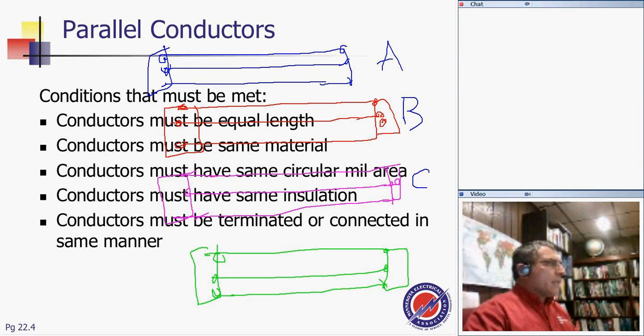These are your conductors that parallel, tied at the end. This is my neutral. This is my neutral. So each of these, these are three conductors. Each one of them, my friends, is 500 kcm. I like 500 kcm. The same thing, 500 kcm, 500 kcm. And let's just say the neutral was smaller, 400 kcm, K, C, M. And it was also three conductors.